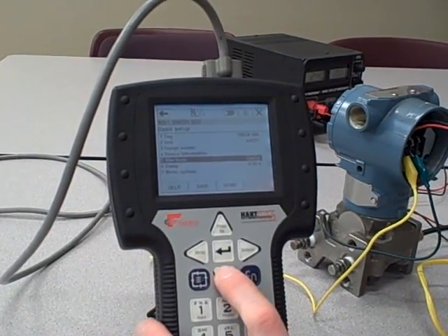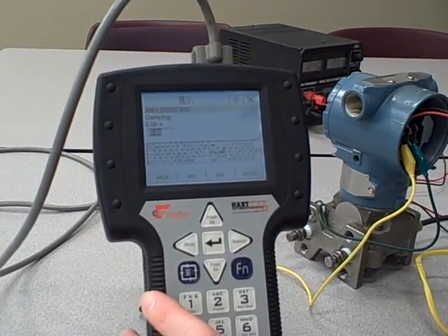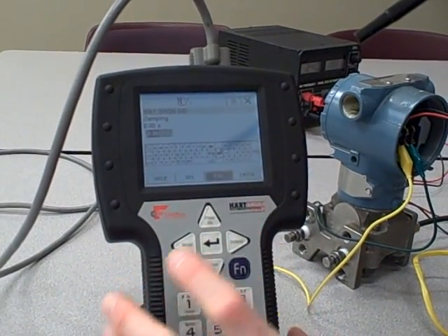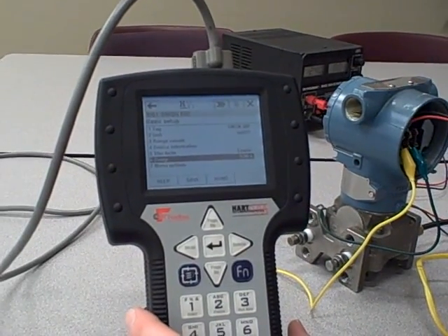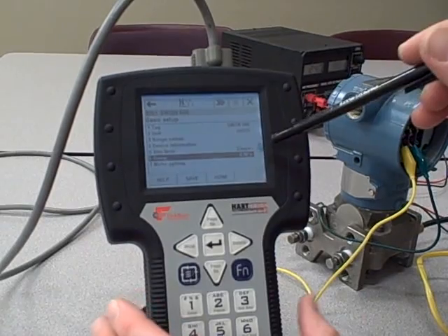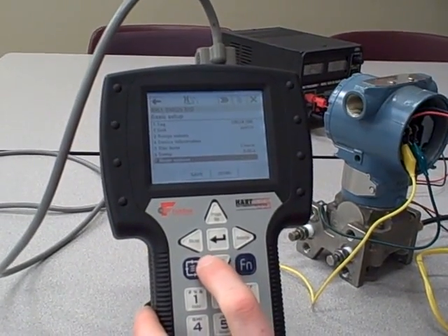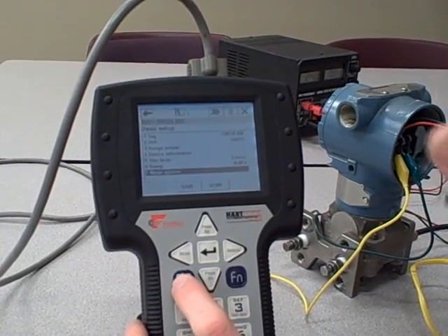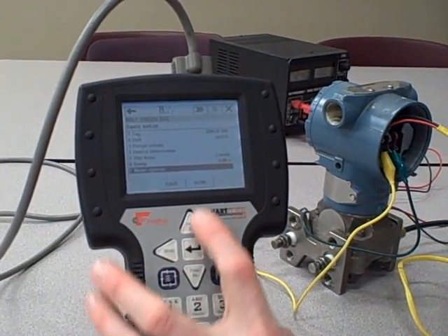We also have Damping. Damping is essentially a low-pass filter function, where we tell the transmitter to ignore or dampen any fluctuating pressures that it sees. That's helpful when you're measuring a pressure that is noisy by nature. And then we have an option here called Meter Options. In case your transmitter has a built-in indicator on the side, you can set various options that the indicator can follow.